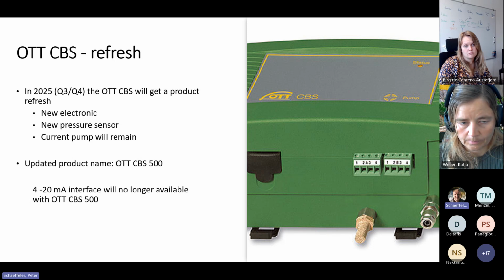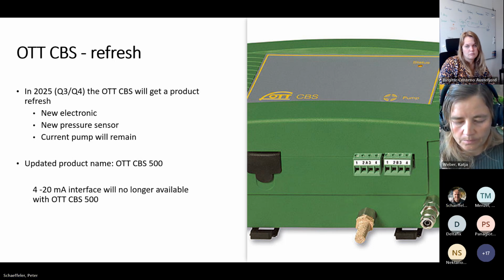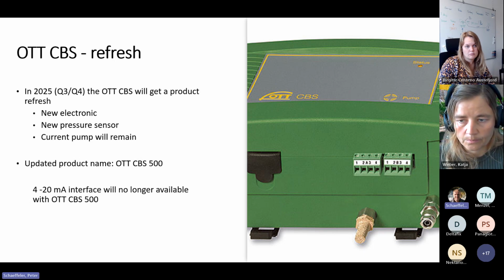The CBS will get a complete new electronic, which will also allow more metadata to be used. It will get a new pressure sensor. What will remain is the current pump we use, because with this pump we have no issues at all - it's a very high quality pump. But besides that, the electronics inside will be completely new. So that doesn't really change what the device does - it adds metadata for the future, but it will still be the existing CBS, reliable as known.